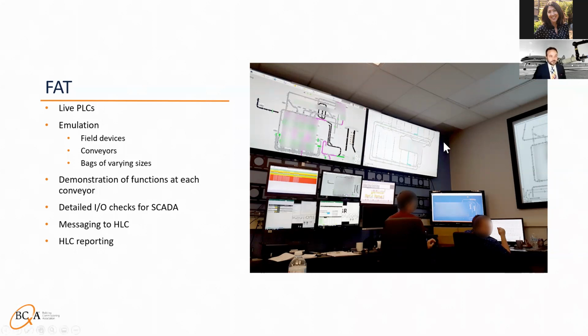In addition, since everything is completely under control, you can, for example, send a known number of bags down a system and then count the correct number of bags, or verify that the correct number of bags have shown on the upper level controls. This is repeated again later on in the field, but for large scale trials it is much easier and cheaper to do at the FAT level. You'll check reports to make sure that the right number of bags have gone to each of their destinations.